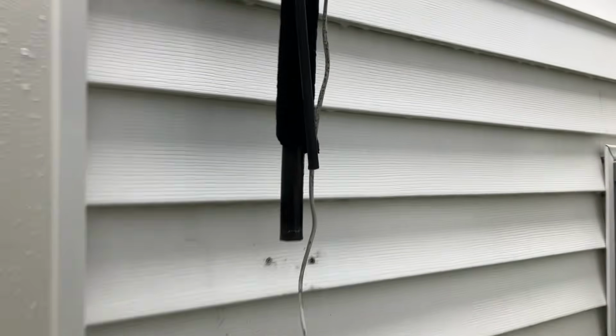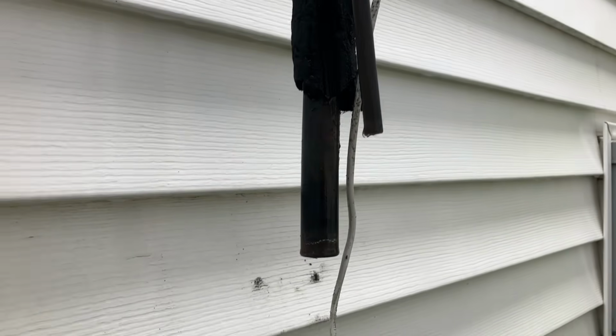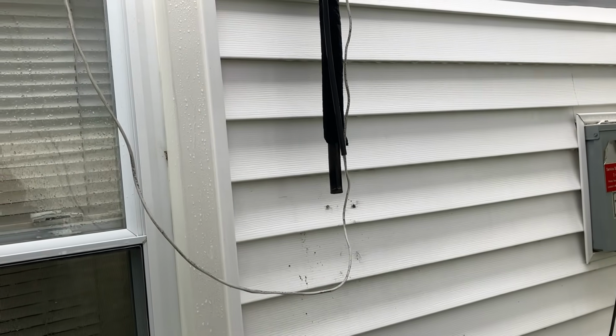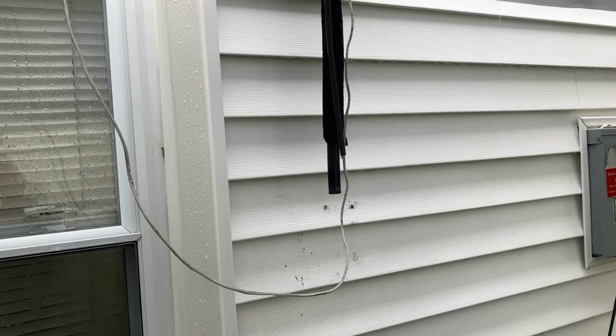All right, I used my tubing cutter and cut the line set, the 7/8 and the 3/8. I'm not worried about anything dripping down into it because it's just water dripping down. I'm good with that. After we used a pipe wiper to remove all the oils from the line set, we should be good to go.